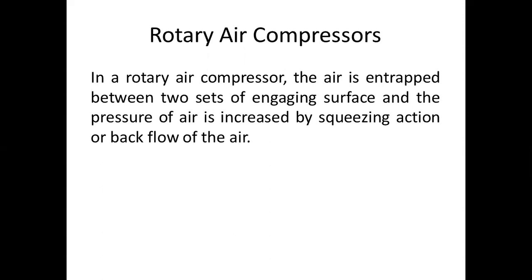This type of rotary air compressor is suitable for large discharge of air at low pressure. The maximum free air discharge is as high as 3000 meter cube per minute. The speed of the air compressor is high. The rotary compressor will supply the air continuously. The size of the compressor is small for the same discharge as compared to the reciprocating air compressor.